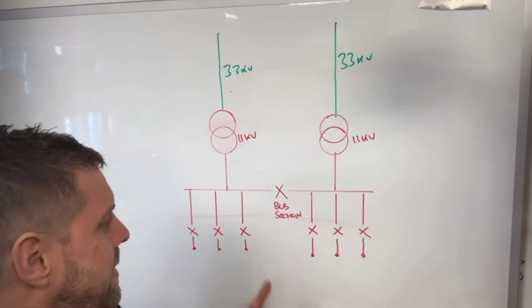In the 11,000 volt switchboard, this happens. Now let me get rid of this bit I'm calling the bus section here - let me remove the bus section, because now what you'll see is we've got a transformer feeding a three-way fuse board, let's think of it like that. So we've got a transformer feeding a three-way fuse board, and another transformer feeding a three-way fuse board. And out of that we take all our supplies to our 11 kV stuff, which we're going to get into.